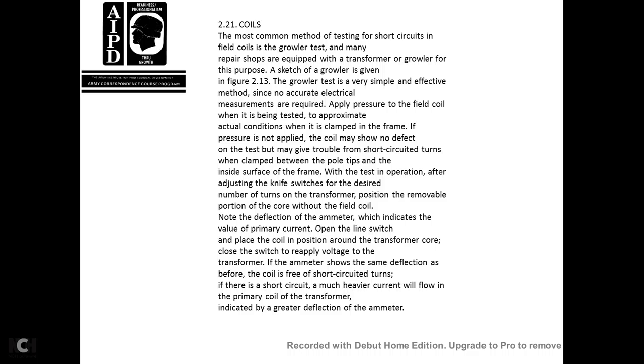Apply pressure to the field coil when it is being tested to approximate actual conditions when clamped in the frame. If the pressure is not applied, the coil may not show the trouble of the short circuit, which turns up when clamped between the pole tips and inside the surface of the frame. When the test is in operation, after adjusting the knife switches to the desired number of turns of the transformer, position the removable portion of the core without the field coil. Note the deflection of the ammeter, which indicates the value of the primary current.